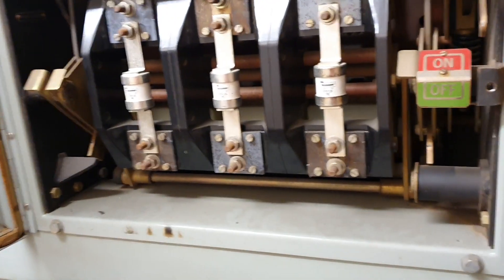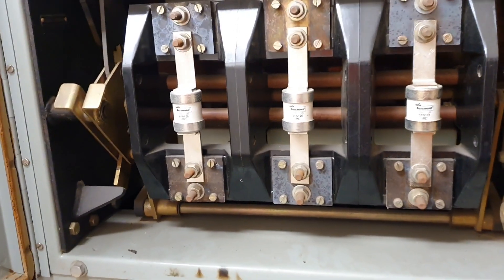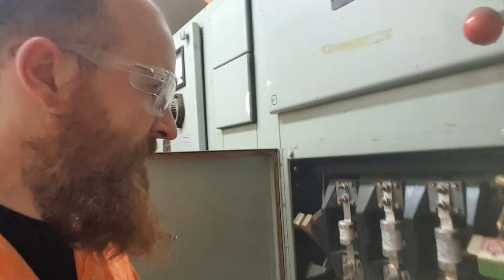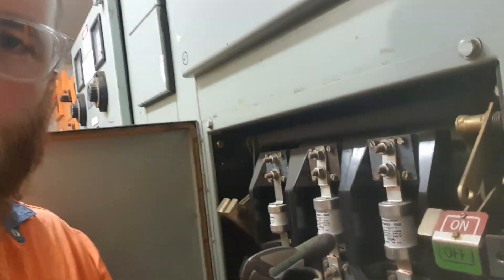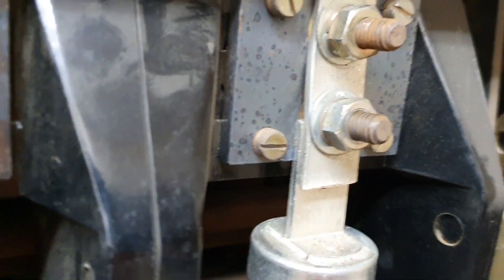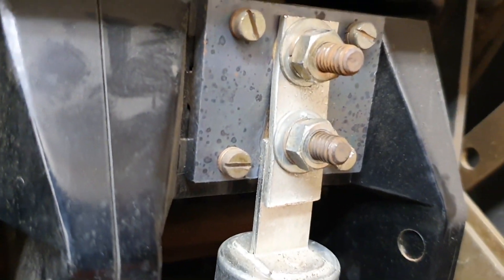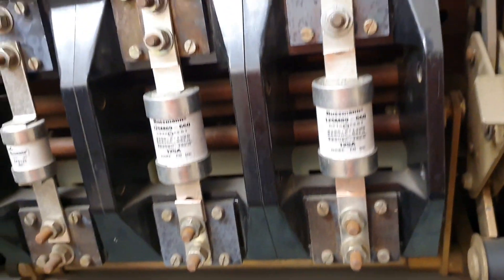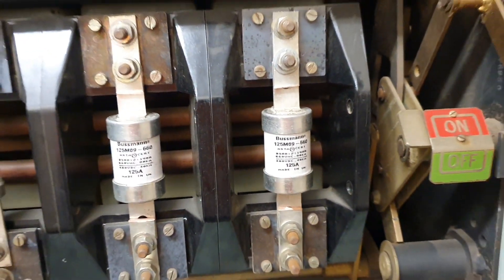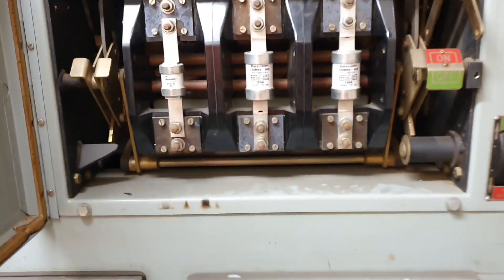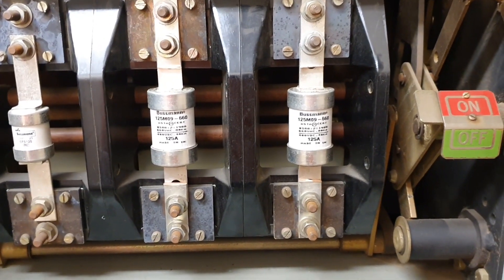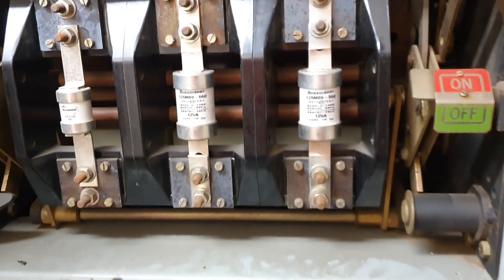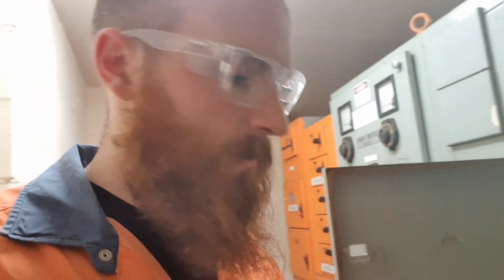So I'll probably have to leave this isolated. We'll replace these fuses. Well, we didn't have the exact right fuses, but we've done a makeshift. I've done a solution here. This is a temporary fix for tonight. So it's critical that these guys get up and running again as soon as possible. I think it will be okay for one night. So yeah, I'll just go megger this circuit. I'll show you that and then pretty well done. It's nearly 10 o'clock, Friday night. I want to get the hell out of here.